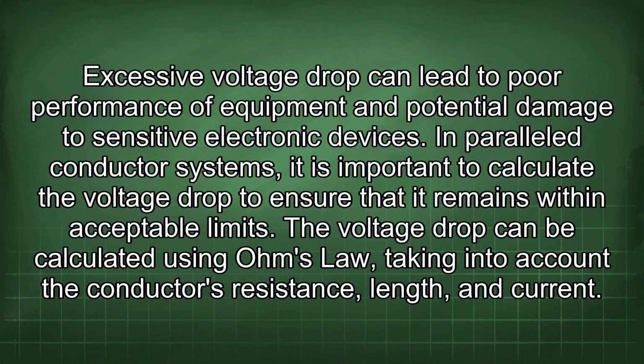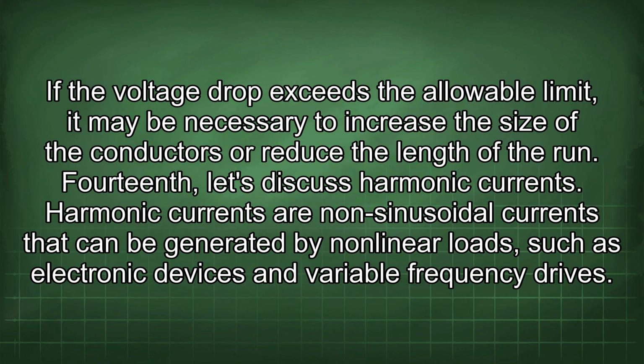The voltage drop can be calculated using Ohm's law, taking into account the conductor's resistance, length, and current. If the voltage drop exceeds the allowable limit, it may be necessary to increase the size of the conductors or reduce the length of the run.